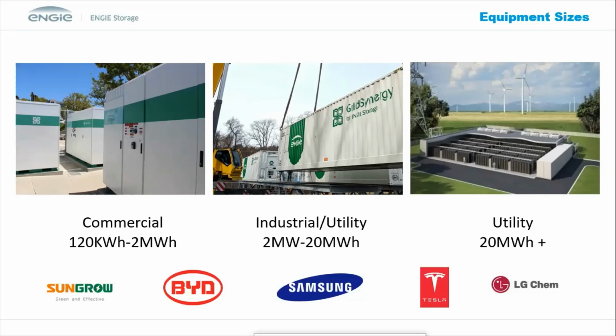When I look at anything in the 2 megawatt and above category, an installed system per megawatt hour, you're looking at high 300s to low $400 per kilowatt hour capacity installed. Two years ago that was over $1,000. So you're seeing a lot of the costs come down and become more economical, which I think will be a challenge for the long duration batteries. But they also have less maintenance and lower degradation rates, so I'm hoping those benefits can offset the cost and financeability issues, and we see more pilots get in and gain traction.